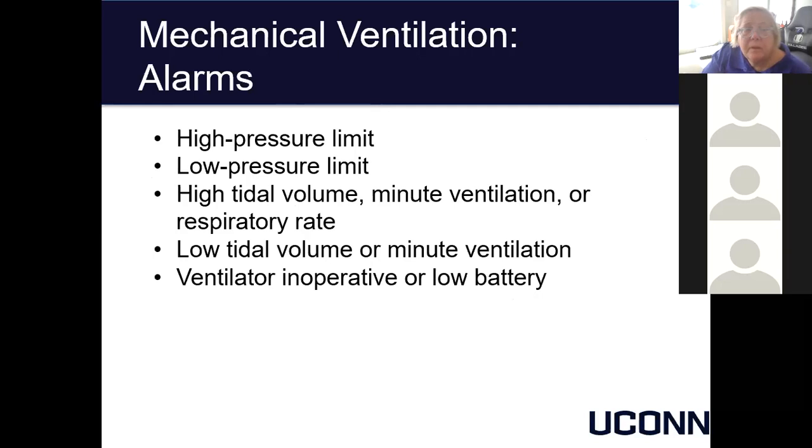High pressure, low pressure, could be low tidal volume, again, that they just couldn't force the whole amount in, or wow, it was really easy and it got that whole amount in. And then there's the whole thing that the ventilator's not working, or it was not plugged in, or the battery is low. But again, no alarm goes ignored. You need to check each alarm and confirm that it's resolved.